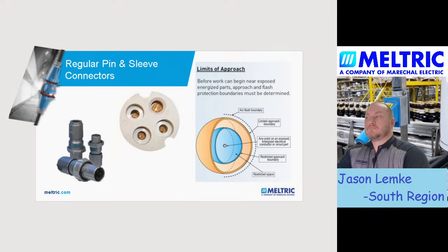So I do want to just reiterate this fact that when you remove a plug from the receptacle on a pin and sleeve, you will have exposure to conductors. And it's that exposure to conductors, particularly ones that we haven't verified zero energy on, where we have this limited approach and are required to have a qualified person or a person who knows what they're doing with the appropriately rated PPE do that operation, do their work in those types of environments.